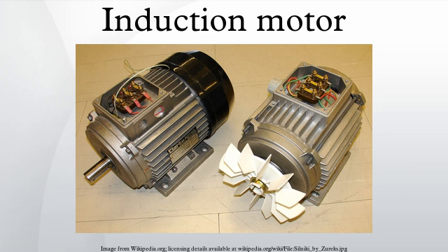Rotation reversal. The method of changing the direction of rotation of an induction motor depends on whether it is a three-phase or single-phase machine. In the case of three-phase, reversal is carried out by swapping connection of any two-phase conductors. In the case of a single-phase motor, it is usually achieved by changing the connection of a starting capacitor from one section of a motor winding to the other. In this latter case, both motor windings are similar.